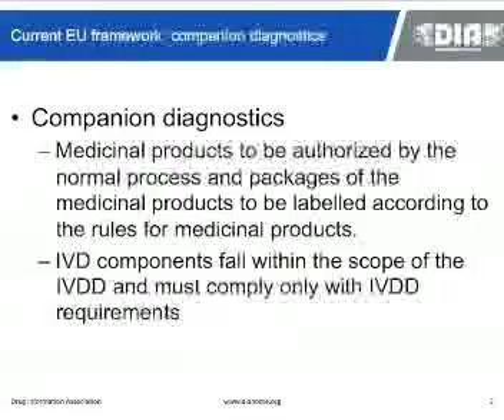So what does that look like? I'm reasoning now from the assumption that you're the manufacturer of an in vitro diagnostic device rather than the accompanying medicinal product. So you found out that you fall within the scope of the in vitro diagnostic directive. Well, then, like with other medical devices, because in Europe in vitro diagnostic medical devices, as the full term is, are a subset of medical devices, you have to demonstrate that it meets the essential requirements that are in the in vitro diagnostic directive, and you also have to demonstrate that you've implemented a quality system that meets the requirements.